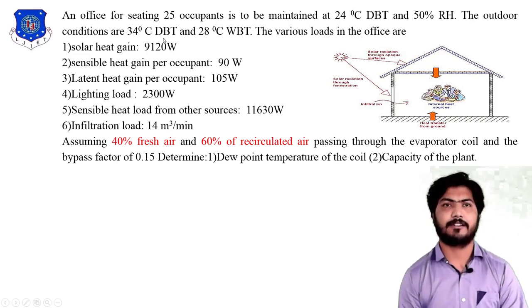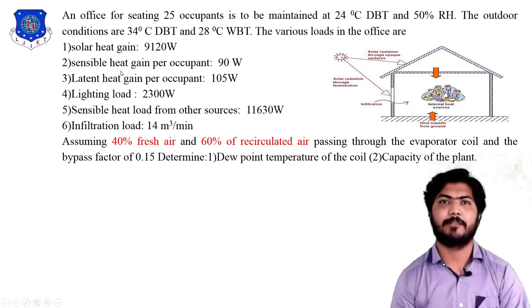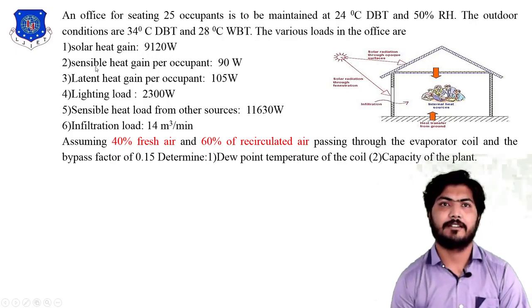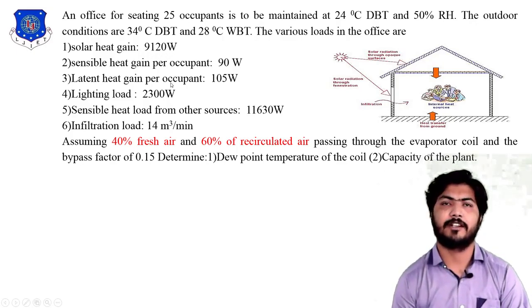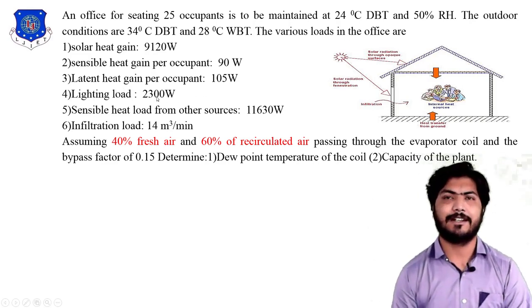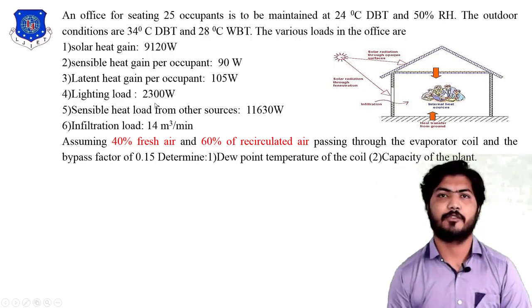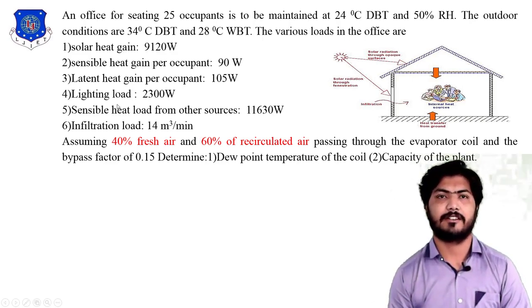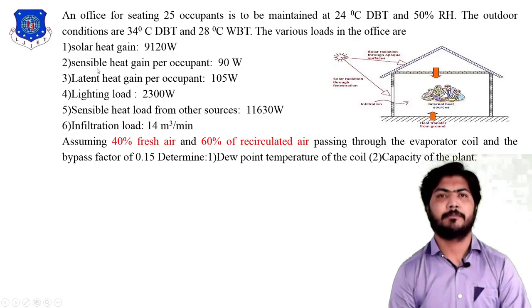The various heat loads in the office are given as follows: solar heat gain from the sun is 9120 W, sensible heat gain per occupant is 90 W, latent heat gain per occupant is 105 W, lighting load is 2300 W, sensible heat gain is 11630 W, and infiltration load is 14 cubic meters per minute.